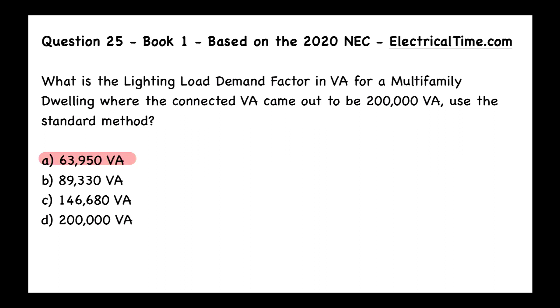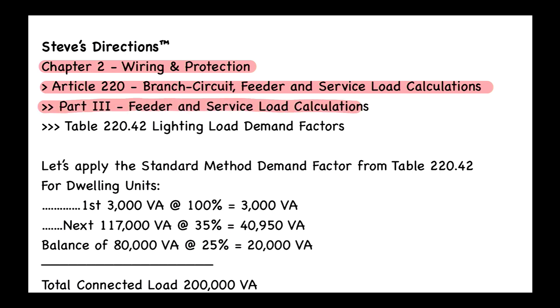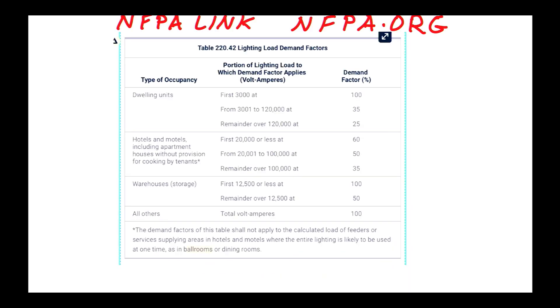The answer is A, and that's going to be 63,950 VA. The first question we ask ourselves is what article are we talking about for this load calculation? That is Article 220, called Branch-Circuit, Feeder and Service Load Calculations, within Chapter 2, Wiring and Protection. Then we find Part 3, Feeder and Service Load Calculations, and Table 220.42, Lighting Load Demand Factors.